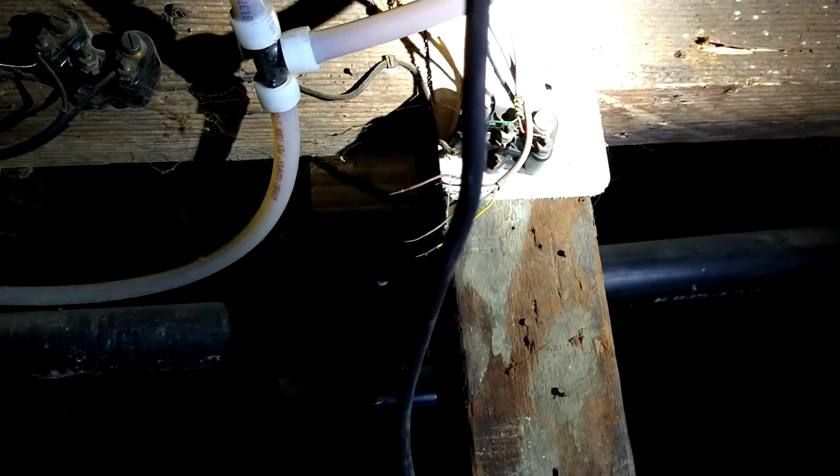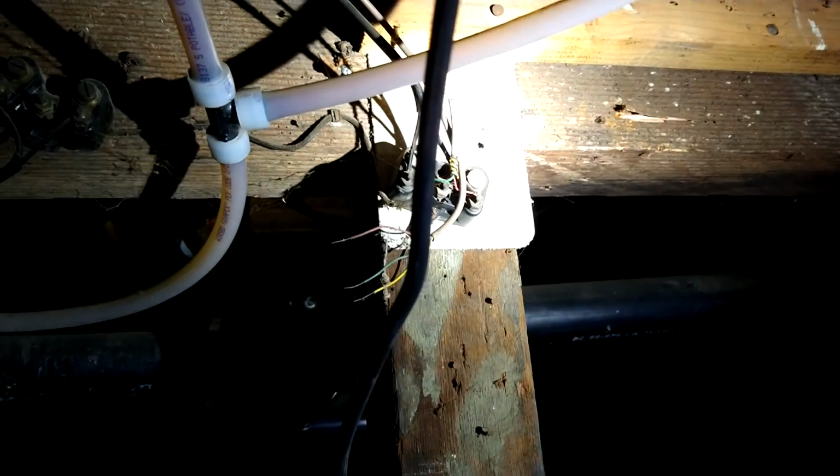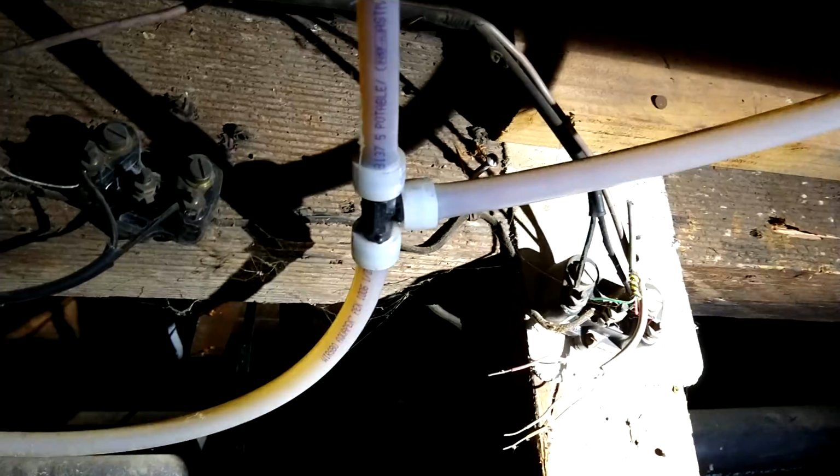I don't know what code book says that's okay. What are we talking about? This here? It's bare wire here. Okay. First of all, that's the old knob and tube, and it's not in a J box. And if it's not in use, all this abandoned wire is supposed to be removed. If it is in use, it shouldn't be bare and hanging out like that and not in a J box. That is not safe. And not only that, look at where it is. I don't think there's any code book that allows you to put plumbing and pipes that close to an electrical fixture.